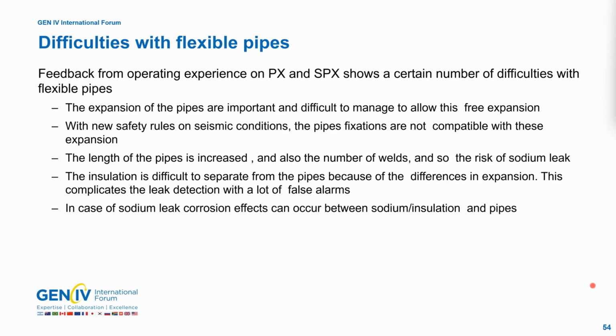With the new safety rules on seismic conditions, the pipe fixations are not compatible with this expansion. If we are firmly bolted on the pipes, you cannot have a free expansion. And if you have a free expansion, it's not possible to have firm bolting for the seismic conditions. The length of the pipe is increased because if you are flexible, you need a big length of pipe, and that increases the number of welds and also the risk of sodium leaks.